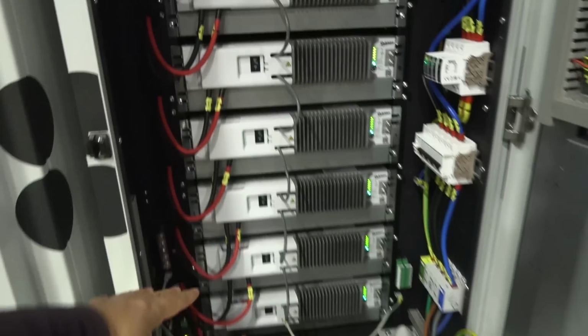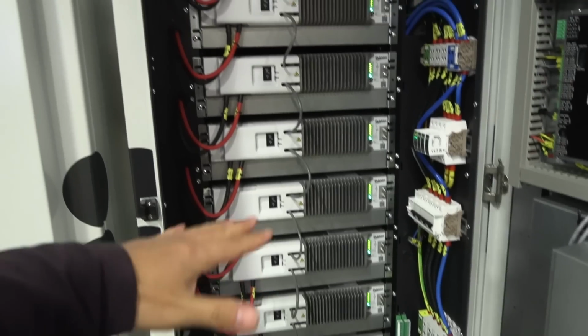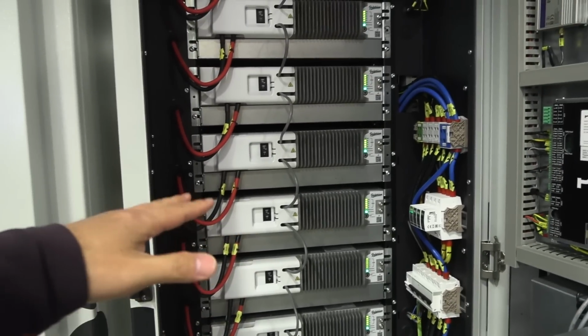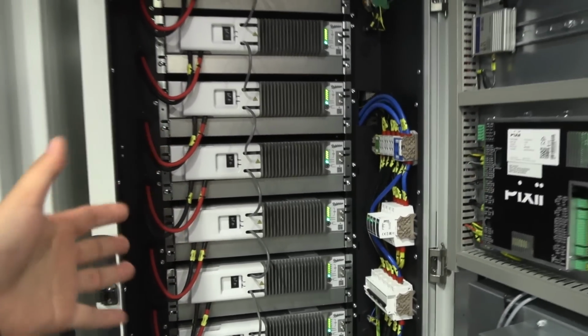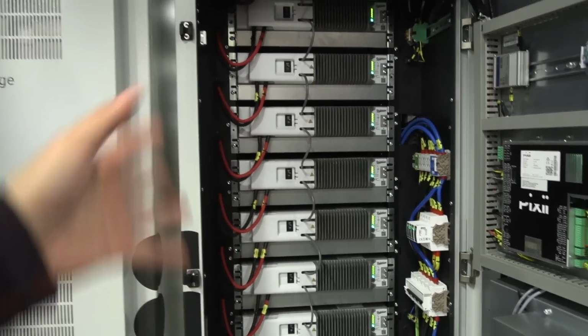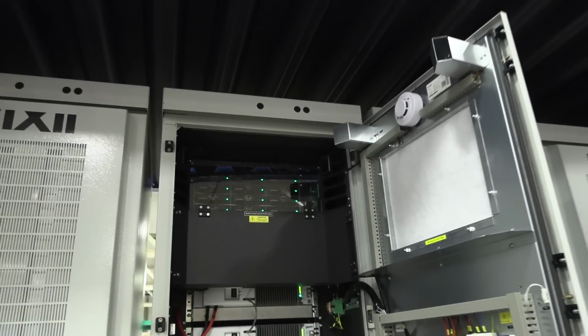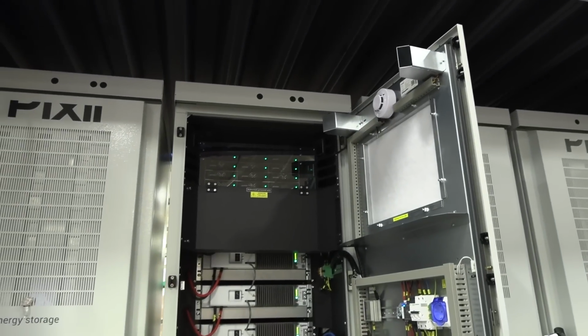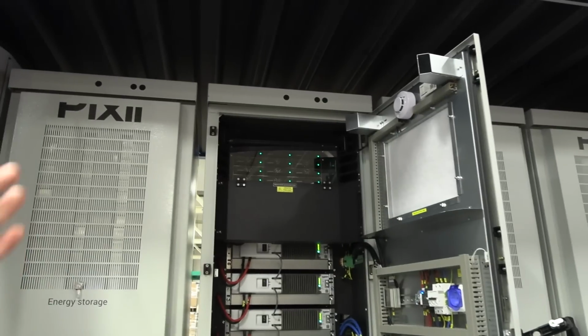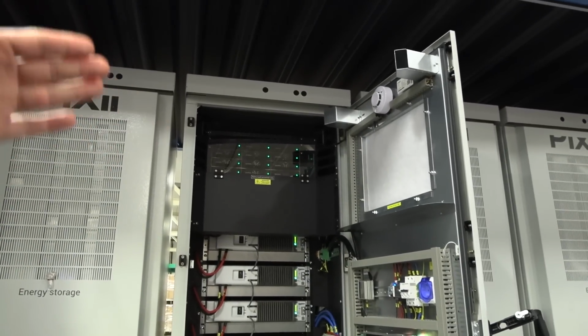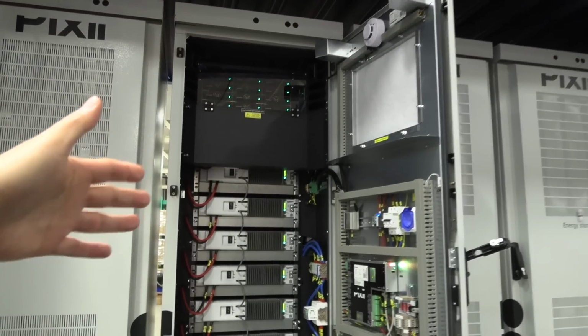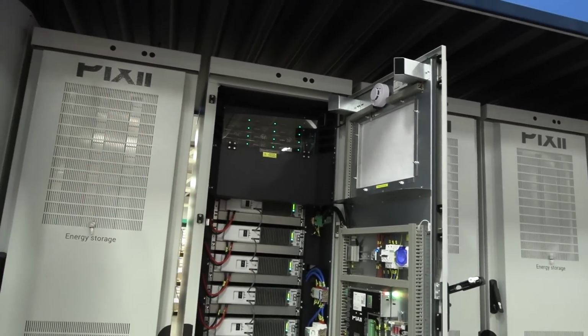Actually, each of these modules operate on only 48 volts, but they're not connected in serial or anything to create some high voltage. It doesn't need to, because up on the top we have the inverters. Two-way inverters, because you transform AC to DC for storing, but also go the other way for discharging.